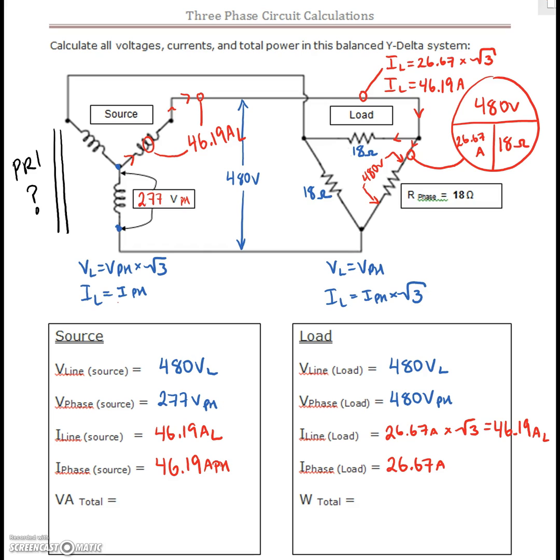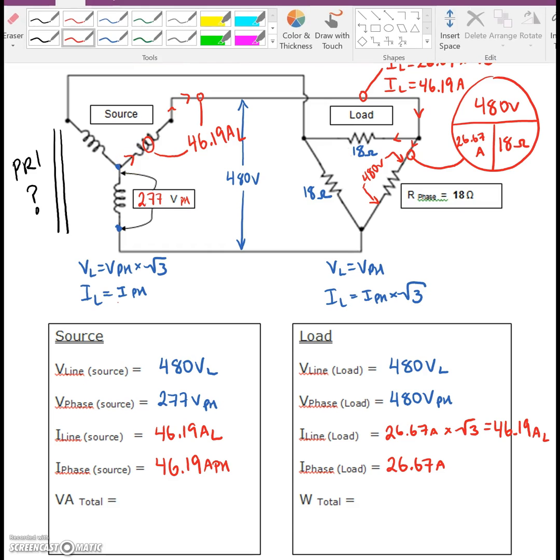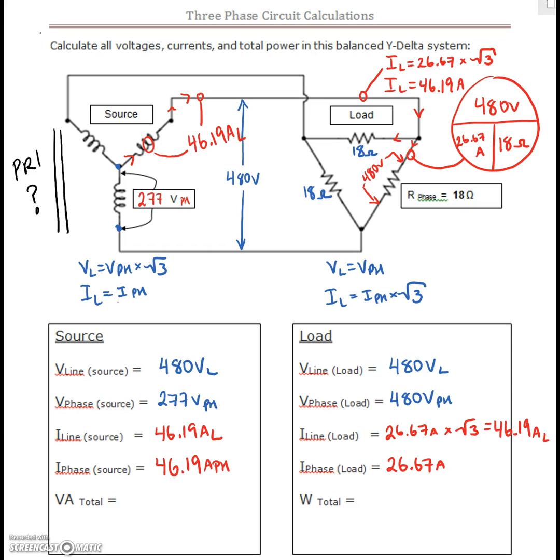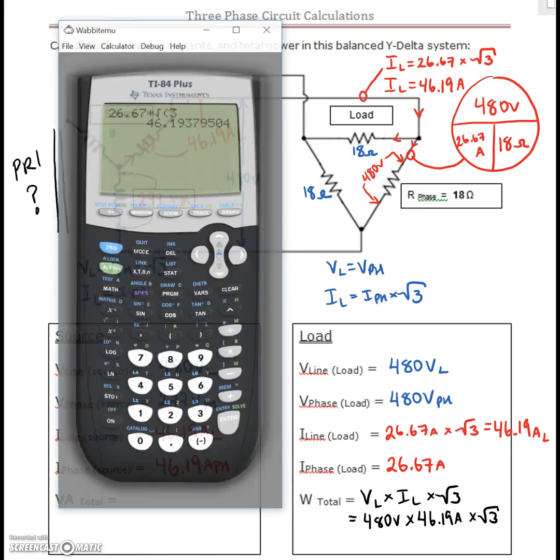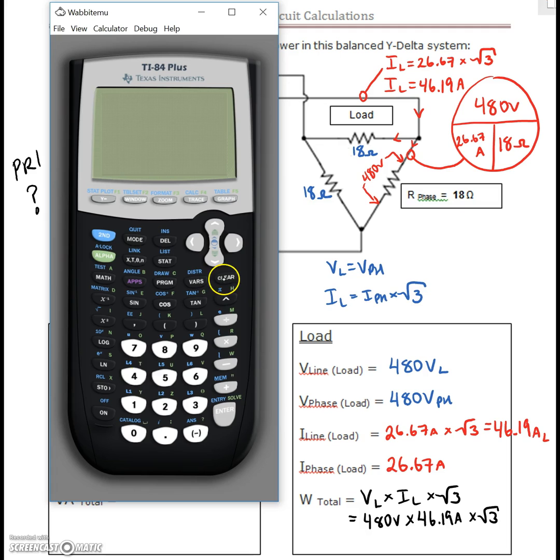Last thing we need to do is find our power values. We have one load being fed by one source here, so these guys will be identical. But we're going to use the two equations to double-check our line and our phase values. We can find our total power by doing V line times I line times root 3. So we've got 480 volts times our line current of 46.19 amps, and we'll multiply that by the square root of 3. That gives us 38,401.64 watts.